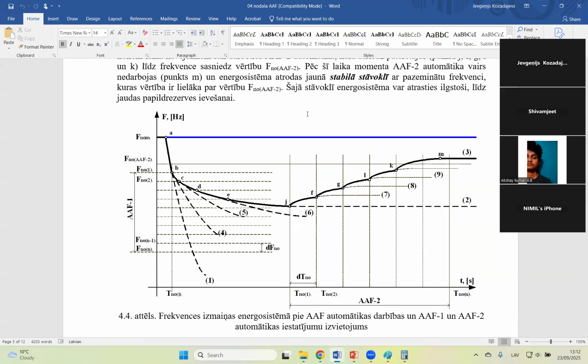And there is a result. So the task to increase this frequency, to restore the frequency, is a dispatcher center task. So the system operator must do this manually. But you see, the dispatcher, the system operator, doesn't have enough time to do this manually, to call the power plants, to plan, to do this. They don't have enough time. That's why if they had one more automation, one more protection, and they restored the frequency, everything was good. But unfortunately, all of this goes to blackout.